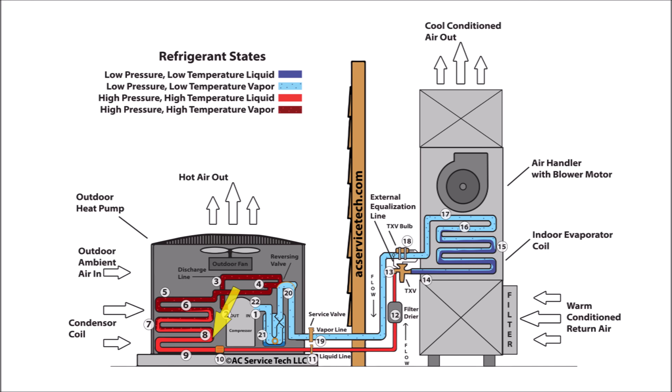In step eight, the saturated refrigerant rejects enough heat energy to turn completely into a liquid. This liquid then starts to lower in temperature — this lowering in temperature in the liquid form is called subcooling. In step nine, the liquid continues to reject heat and lower in temperature as it travels through the condenser; the refrigerant is in the process of subcooling.